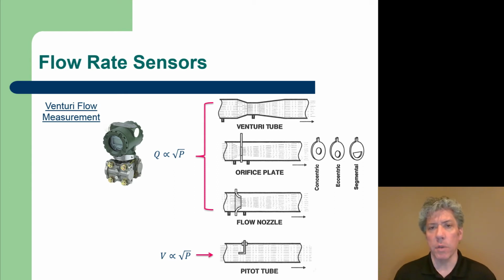But flow nozzles are sort of like a mixture between a Venturi and an orifice plate. They're not as expensive as a Venturi tube. They're also more flexible. A lot of times you can take a flow nozzle and change it out to a different nozzle. And because of the rounded inlet, there's less pressure loss. There's not as much pressure recovery typically as in a Venturi tube, but then the cost is typically somewhere between a Venturi tube and a simple orifice plate device. But the principle in all of these is the same, and that is that you cause a pressure change, and from that pressure change you can calibrate and figure out the flow rate Q. And now this is a volume flow rate, understand, not a mass flow rate. If you've ever looked at a small aircraft, you've probably noticed pitot tubes on the wing, though you may not have known what they were.